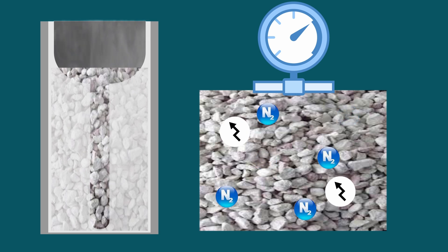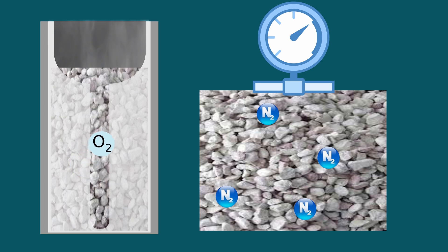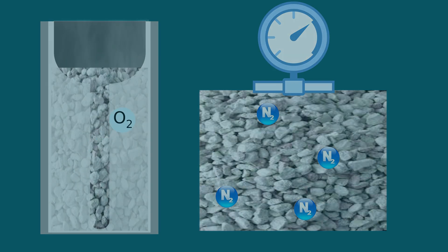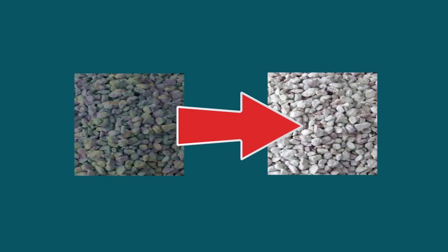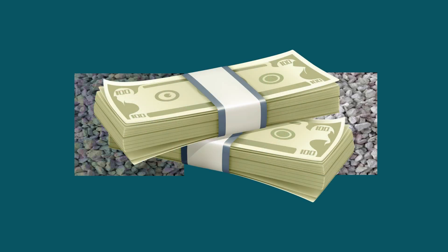Zeolite smoothly absorbs nitrogen, but its absorptivity is gradually exhausted and the efficiency of generating concentrated oxygen decreases. In this case, zeolite should be replaced with a new one, which requires additional financial costs for the purchase of new zeolite and disposal of spent zeolite.